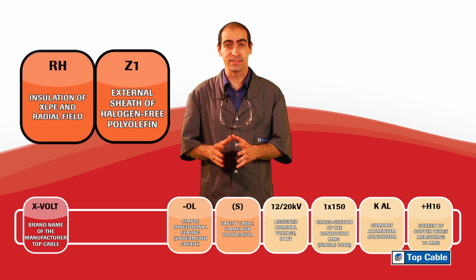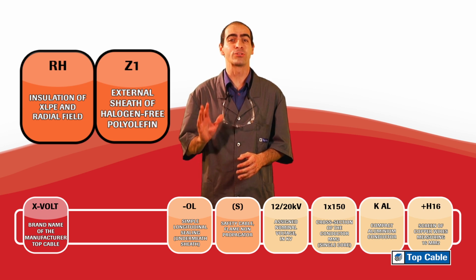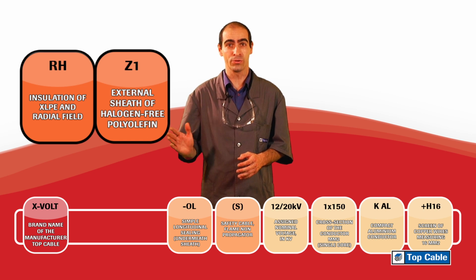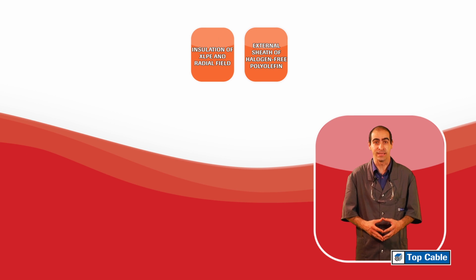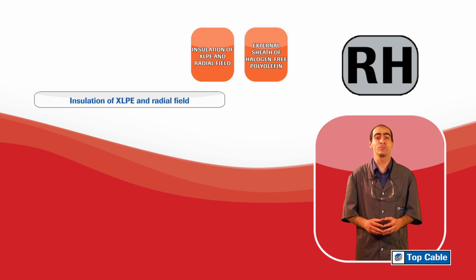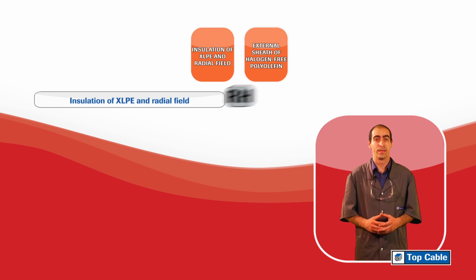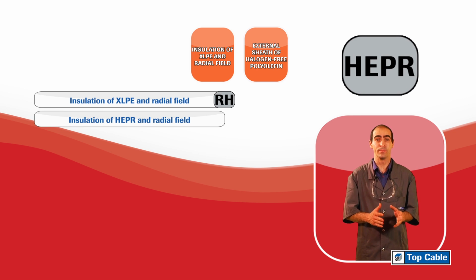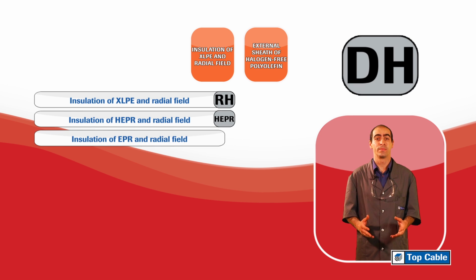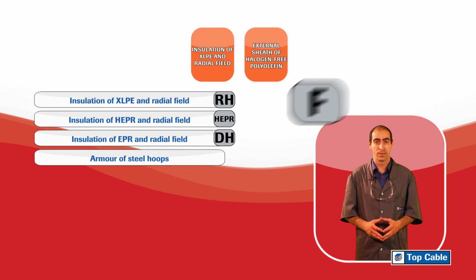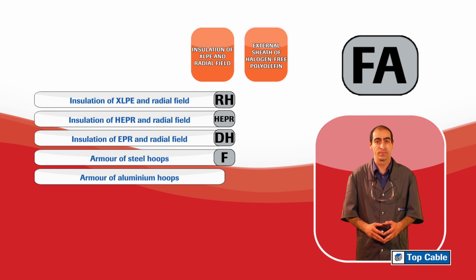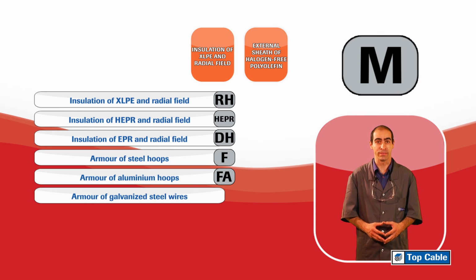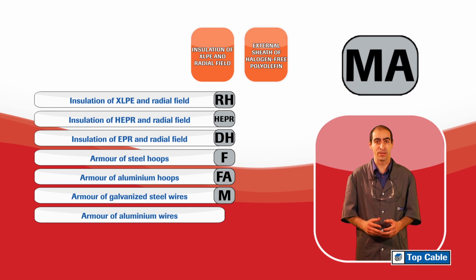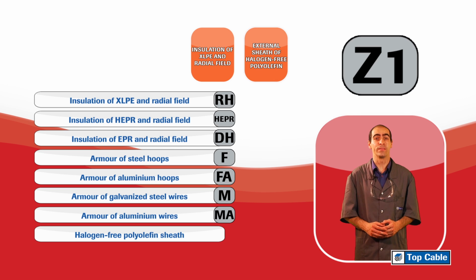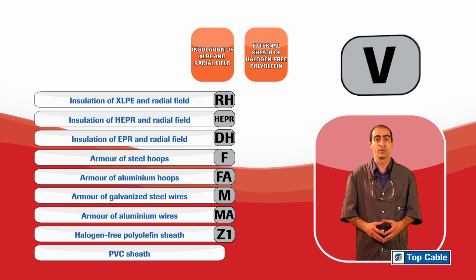After the brand name, the first block, RHZ1 in the example, refers to the cable layers, always from the inside outwards. The meaning of each letter is: RH, insulation of XLPE and radial field. HEPR, insulation of HEPR and radial field. DH, insulation of EPR and radial field. F, armor of steel hoops. FA, armor of aluminium hoops. M, armor of galvanized steel wires. MA, armor of aluminium wires. Z1, halogen-free polyolefin sheath. V, PVC sheath.